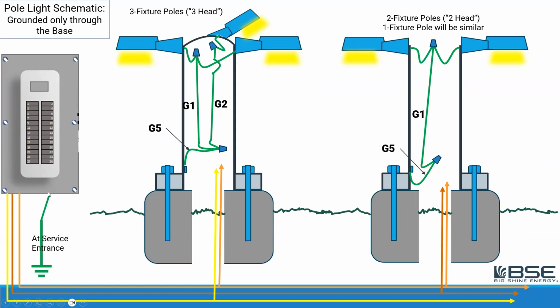The panel itself is grounded, but there's no ground connection that directly connects from these poles or the base of the pole back to this panel. The only connection would be through the dirt. So this is the situation I was talking about: if one of these green grounding conductors were to have a fault, or let's say something short-circuited inside the light fixture, you're probably not going to trip the breaker and the pole might be energized.